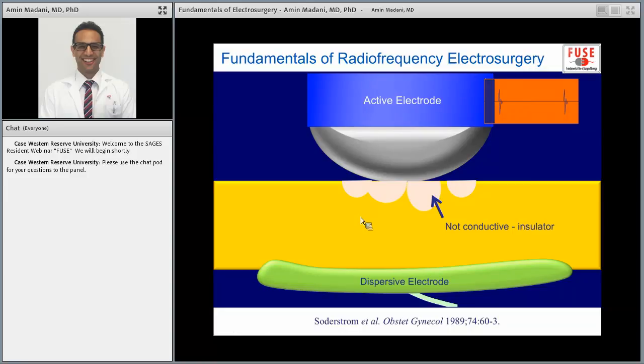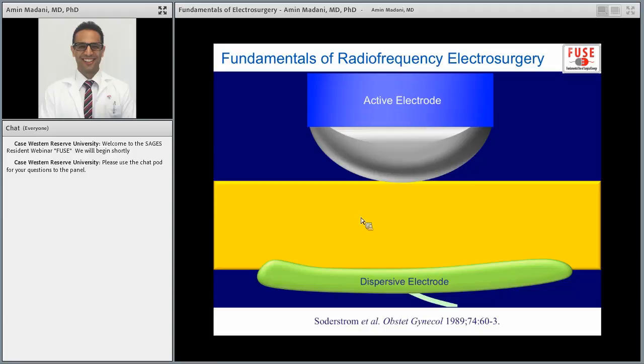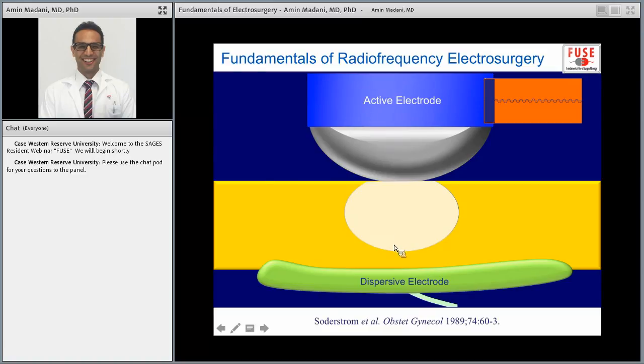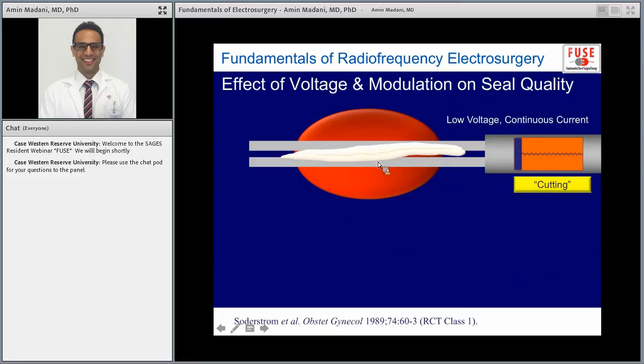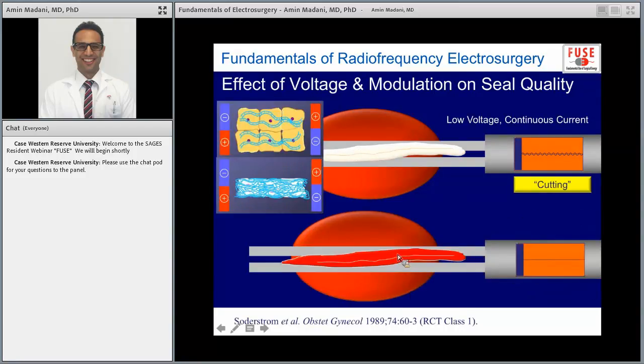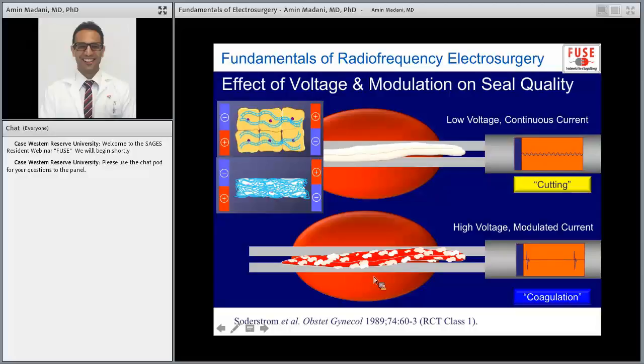It's kind of like throwing a steak into a very hot pan with a very high temperature. The surface is going to burn, but the inside is not going to cook very much. In contrast, when you use cut, you activate it, it's going to slowly cook the full thickness of that tissue. And so you end up getting this homogeneous vessel seal. Sure, it takes a little bit longer for this seal to form because it's lower energy, but it does a much better job. It's more homogeneous, and it seals the vessel better. So low voltage, slow, but much more homogeneous, a nice seal. And with coag, you get something very heterogeneous, and it doesn't seal the vessel very well. Now, for very small bleeders, you're not going to notice very much of an effect. They're both probably going to be the same thing. But when you have bigger vessels, this becomes important.